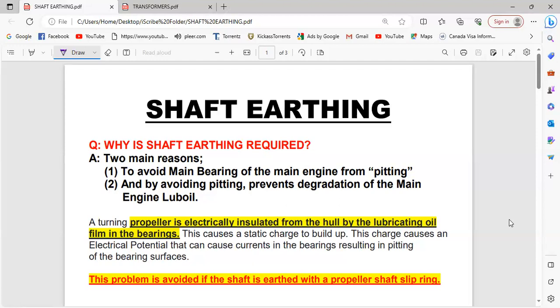Number one, if that thing gets pitted, the bearing gets pitted. Why pitting happens is because sparks or arcs are created, like we saw in the high voltage setup and in the ACB. That means certain metallic contacts are away from each other, so the main bearing and your shaft are away from each other, but the gap is so close that any buildup of electricity will arc across. Whenever there is arcing, heat is developed, and because of that heat, hot spots are formed.